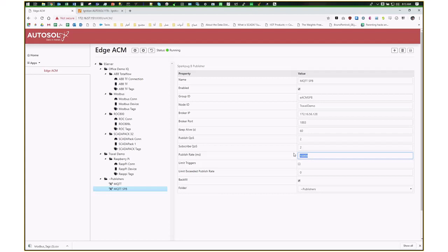I could have a device that's got a 1 second poll rate, but a publish rate of 1 hour. So I haven't done the math yet on how many milliseconds that is, but I could put 1 hour here, which means that MQTT Sparkplug B would then send up 3,600 backfilled data to my HMI at a time.